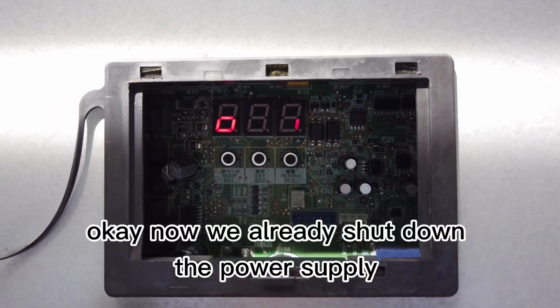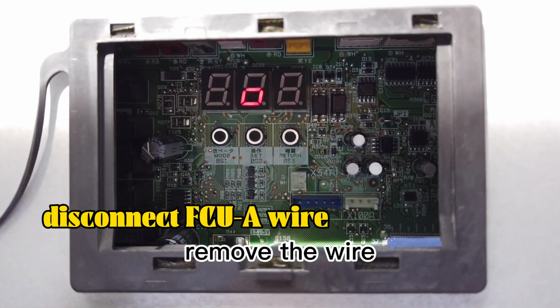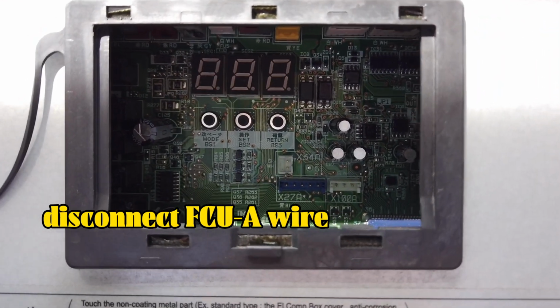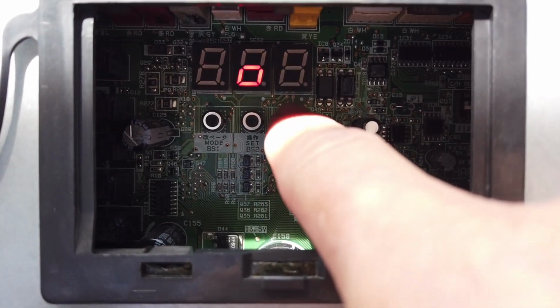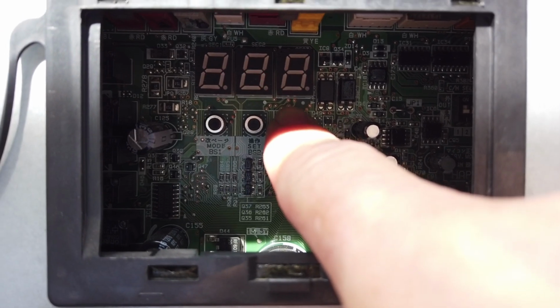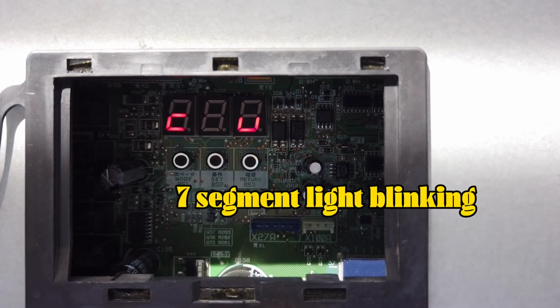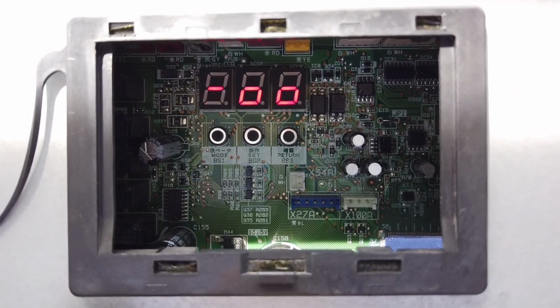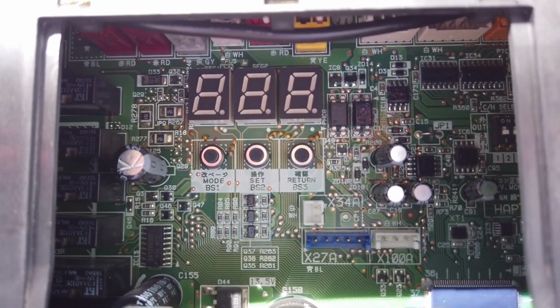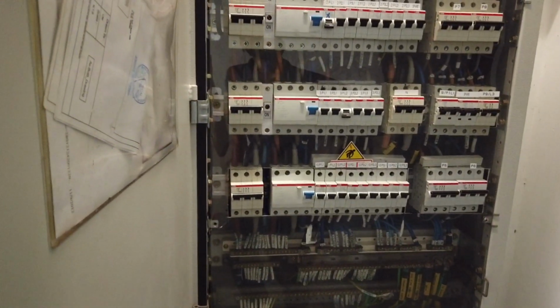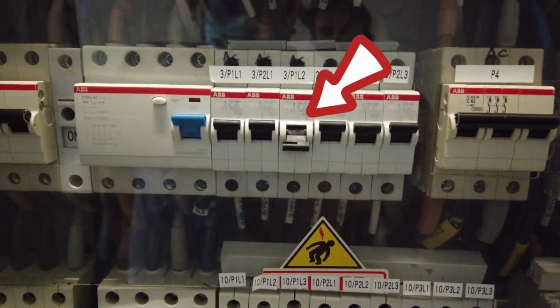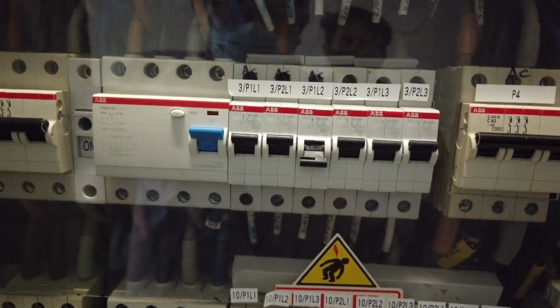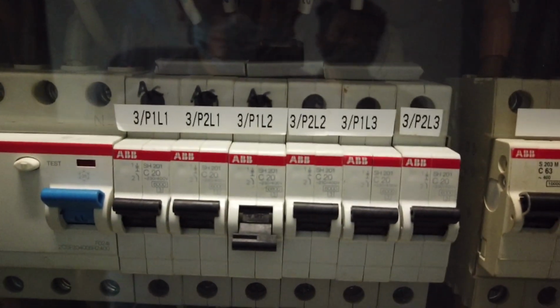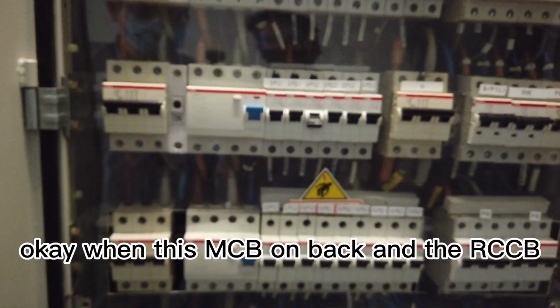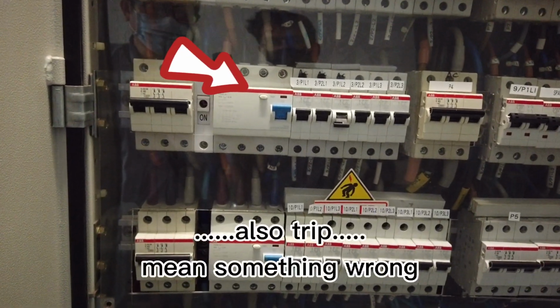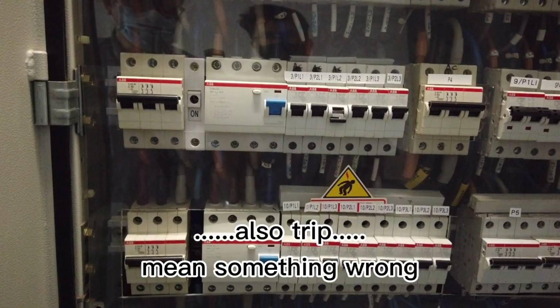Okay, now we already shut down and removed the wire. We try to reset. Light off. Okay, we found this trip MCB, 3/P1L2. When this MCB is switched back on, the RCCB also trips. Means got something wrong, there is a short circuit.